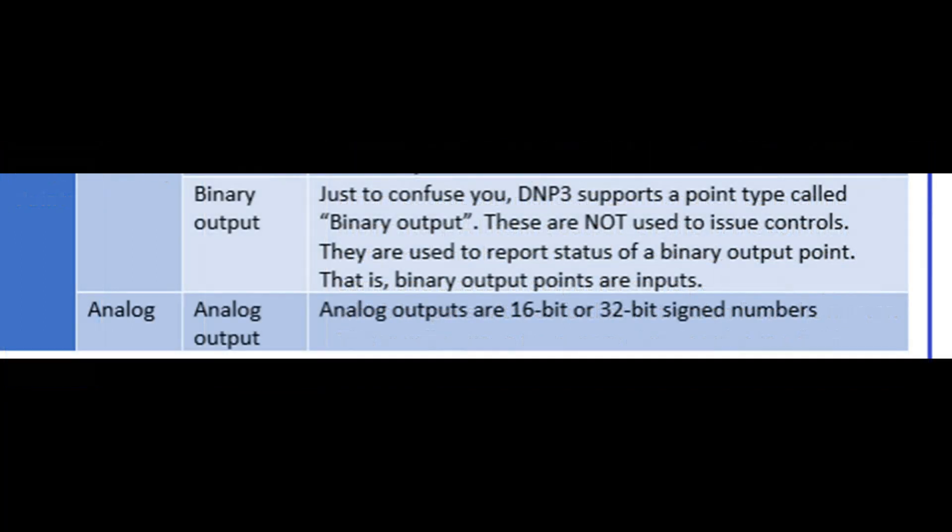DNP3 also supports a point type called binary output, but these are not used to issue controls — they are used to report the status of a binary output point. So a binary output point is actually an input. For analog output types, SCADA analog outputs are simply called analog outputs in DNP3 and are 16 or 32-bit signed numbers.